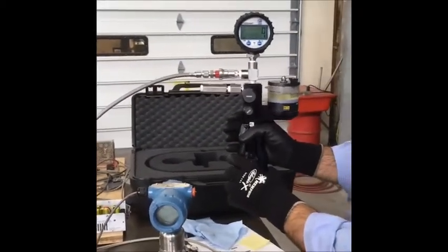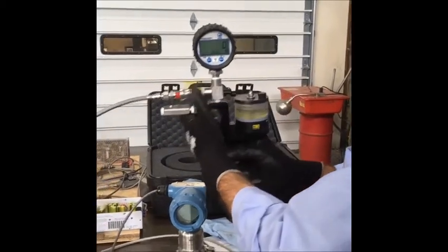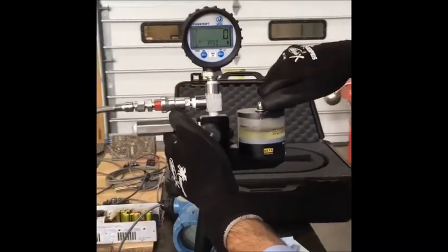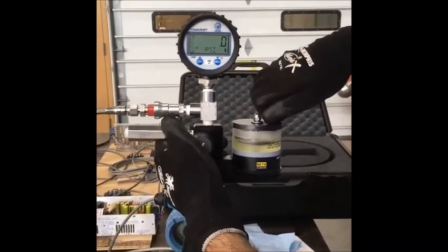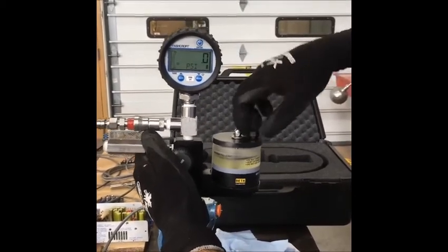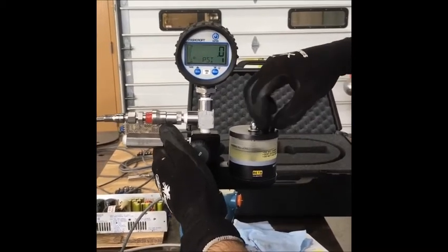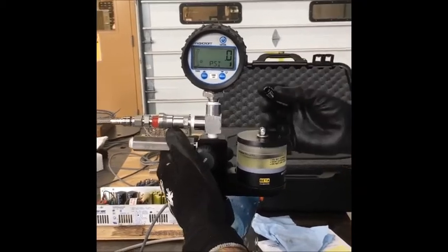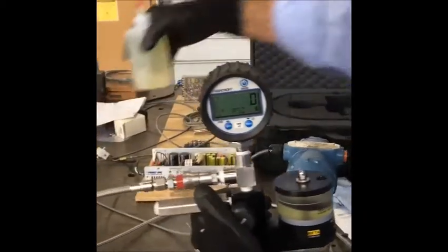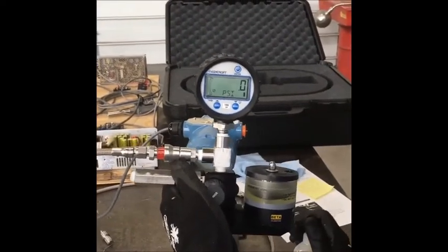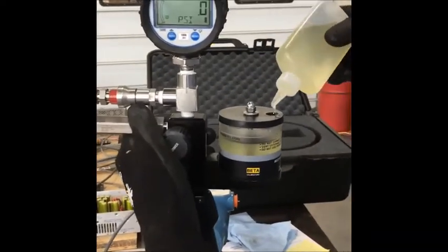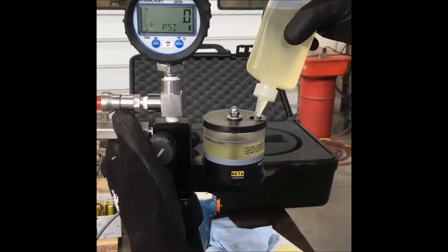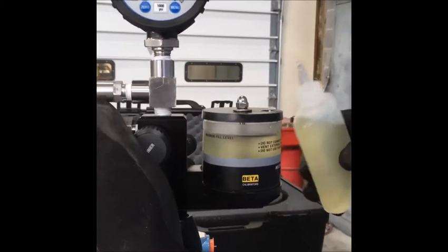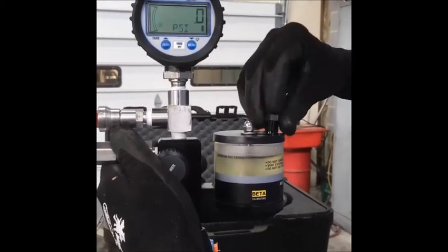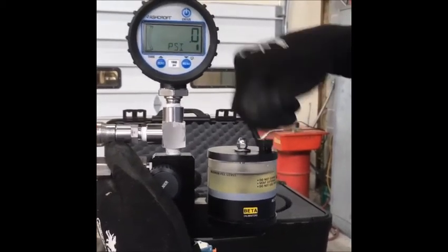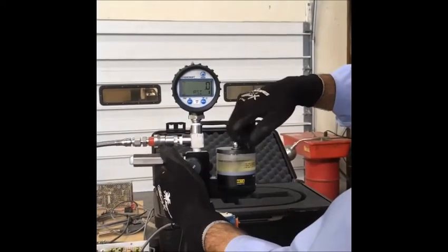Okay, so at that point, our pump is pretty much ready to go. Now, I'd already put oil in this. I should show that part. The pump is made to be used with refrigeration oil, and we recommend that whatever oil is being used in the system that you're to calibrate, that you can use that in the calibration pump. So you have to remove this little plastic plug. I'll set that aside. We've already put our refrigeration oil in a small bottle here to make it easy to fill our pump. And then we will just put refrigeration oil up to the fill line in the pump so that we're ready to go. So there's pretty much full. At that point, we'll stop, and we'll put our plug just loosely back in the hole. Doesn't have to be real tight. So that's pretty much ready to go at that point.